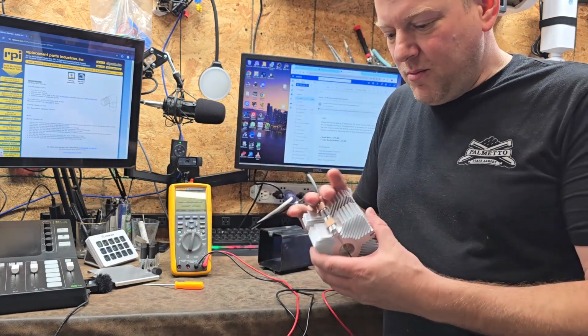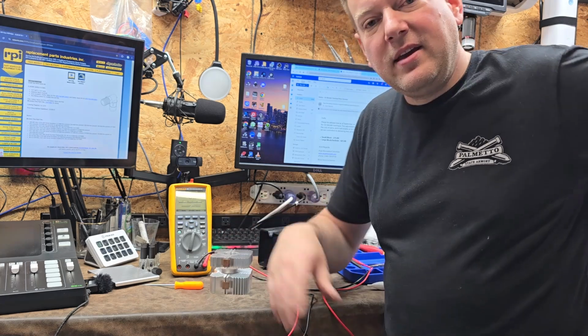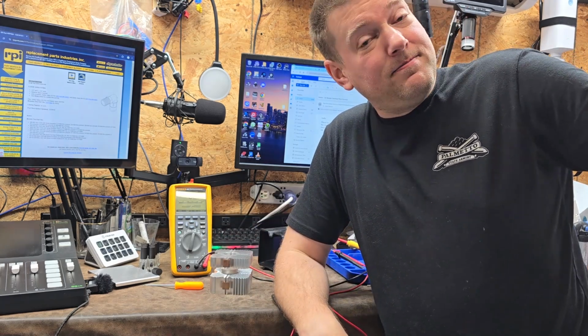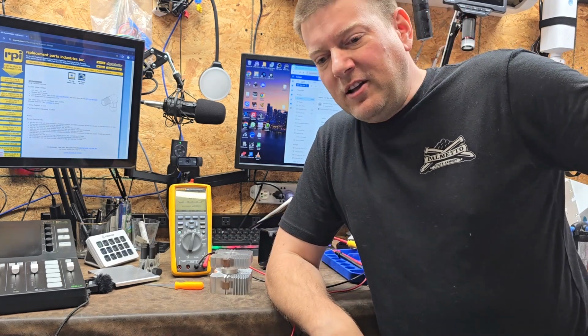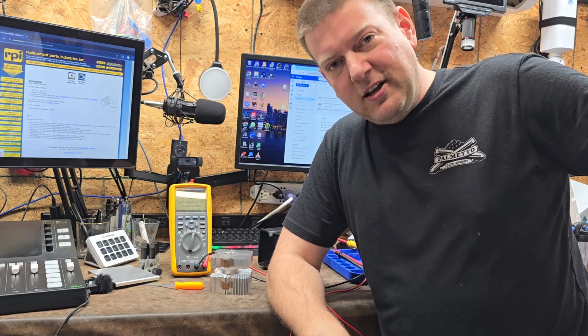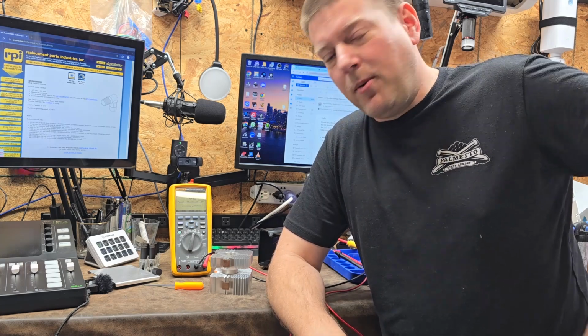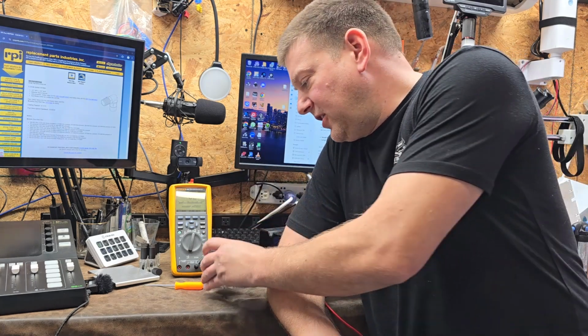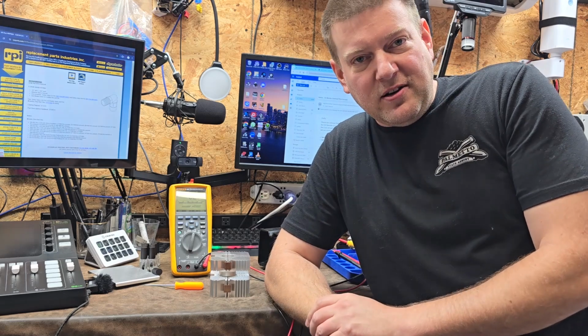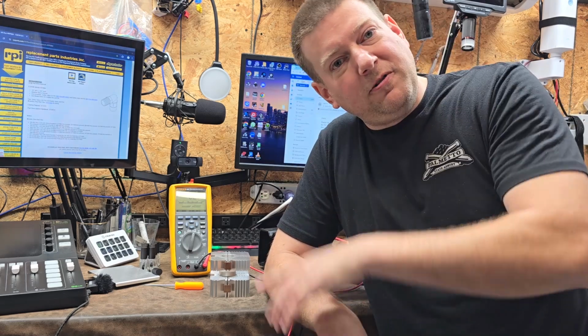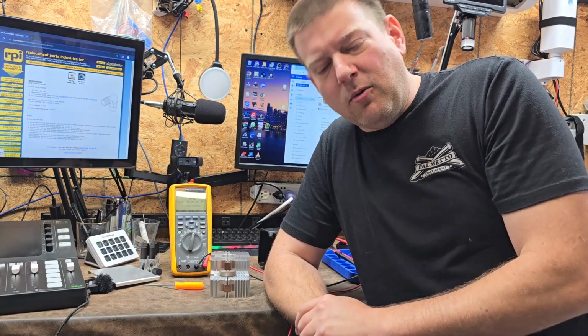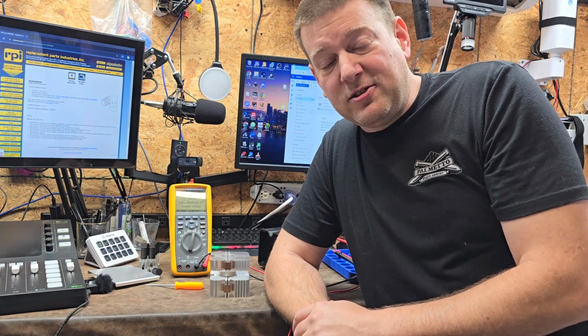Start with the bulb, and we're going to clean the fans and get it back together and test it out. There you go folks — clean your power supplies, clean the fans, and make sure you do a physical inspection on the bulb during the PM. Check to make sure there's no discoloration of the parabolic reflector, and if there is, replace that bulb, because it's getting out of spec and getting old, and it's just going to cause other failures of other components, as you've seen today.